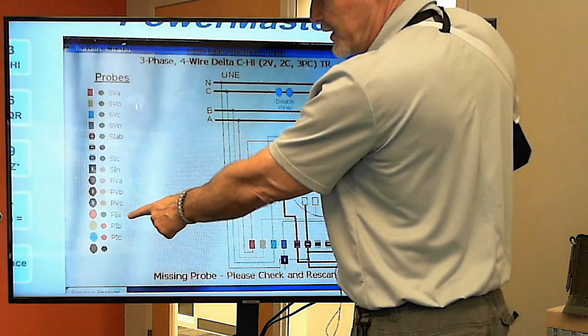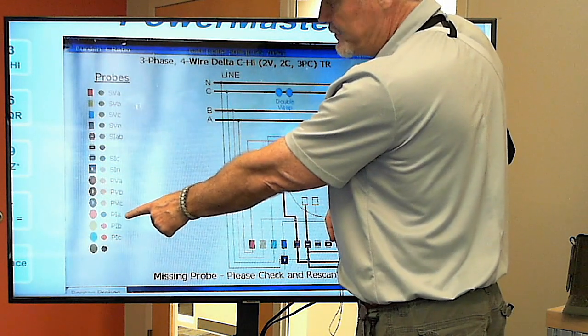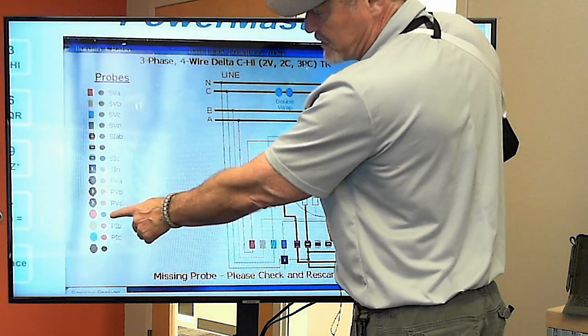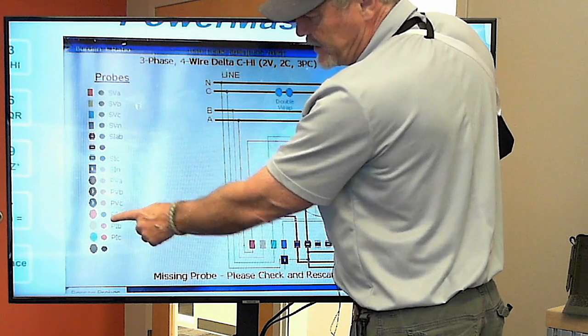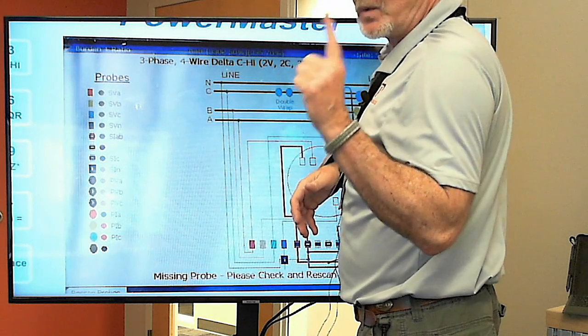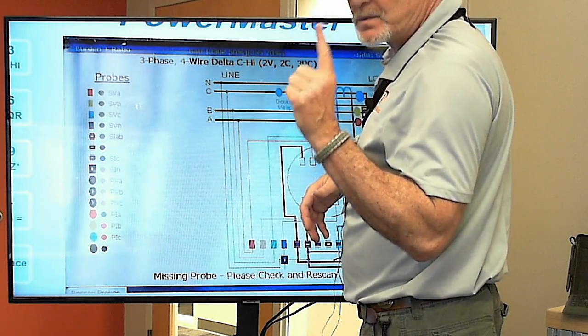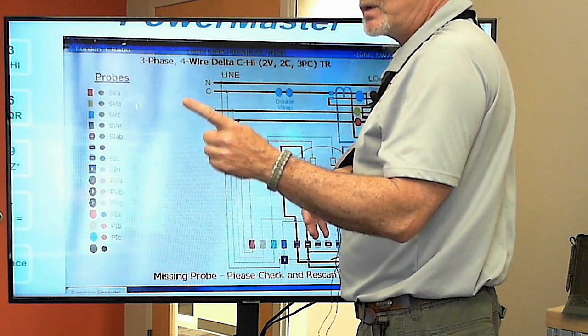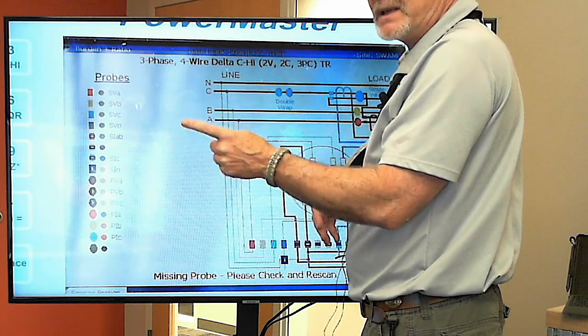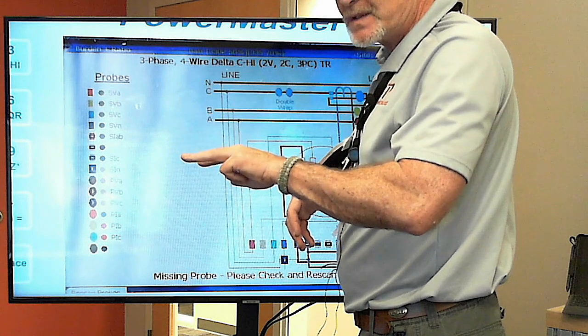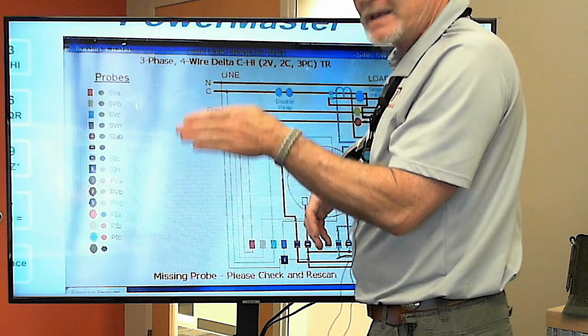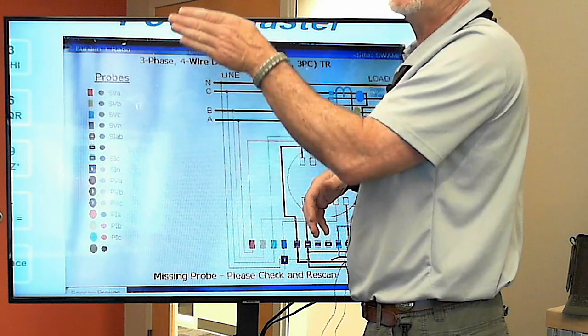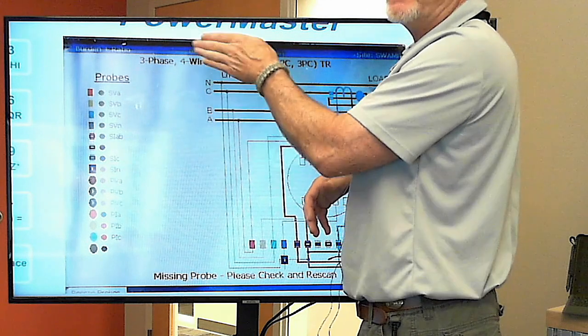If you look down here in the lower part of the screen, we've talked about this before. Solid green, because right now he's got a high volt probe connected to just A phase, which is what you're supposed to do. You don't move it to B and C phase when you test those connections.